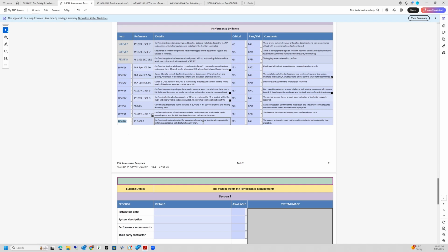If we're setting off detectors to activate smoke control or air conditioning shutdown, we've got to verify what indication we're getting on the panel. And in some cases, we've got to confirm the time delays of the indication on the panel, the time delays of the operation of the fan, which is often done by the mechanical person.